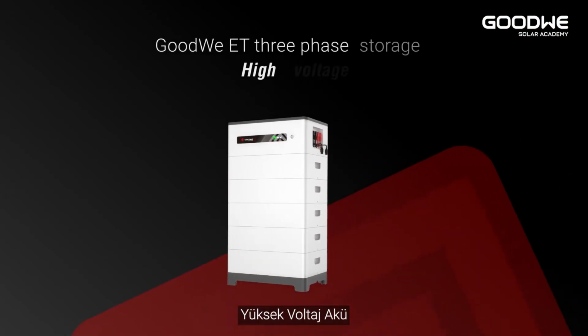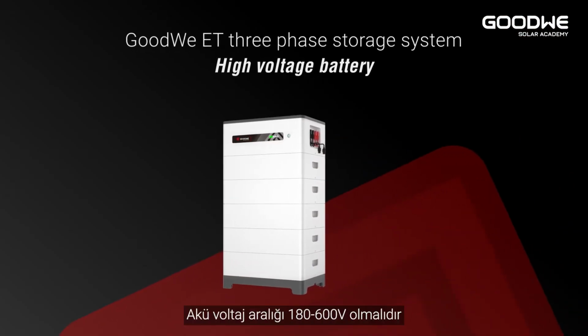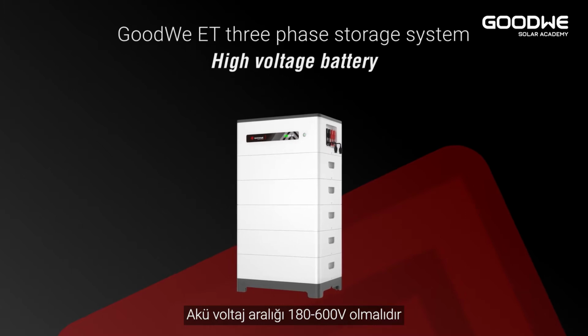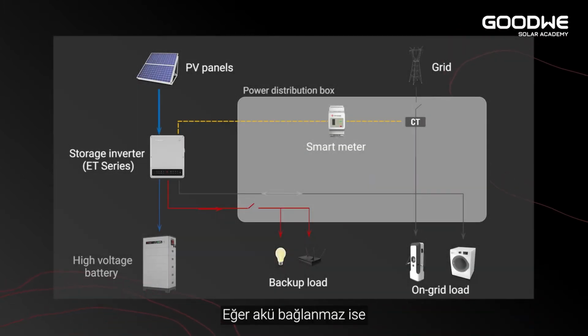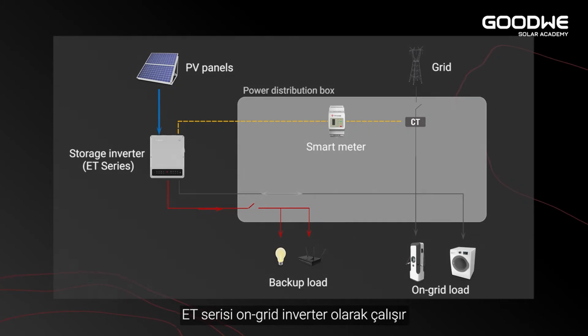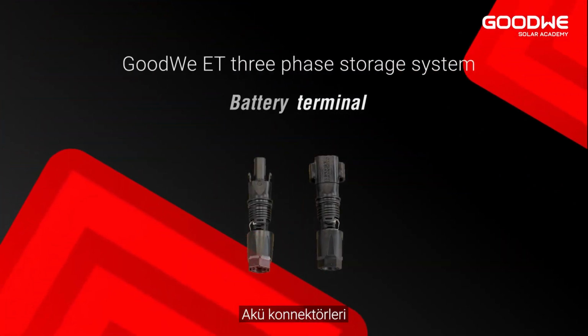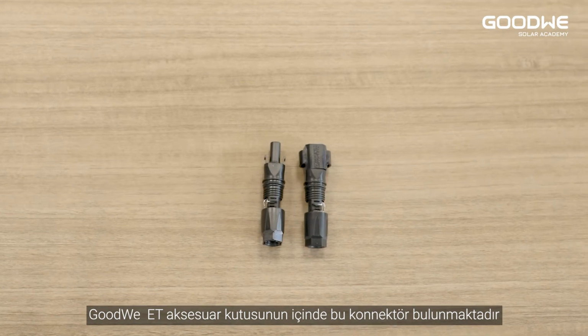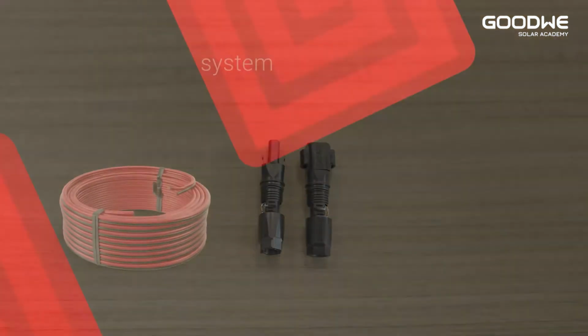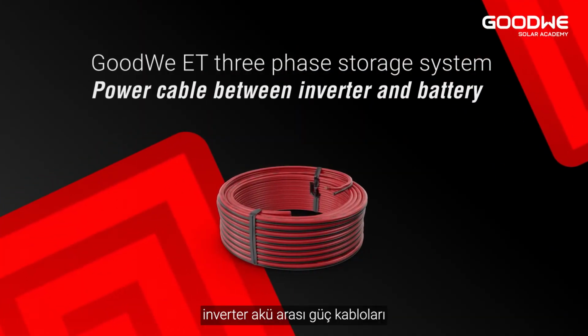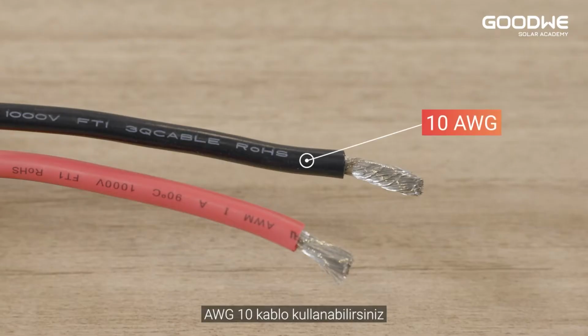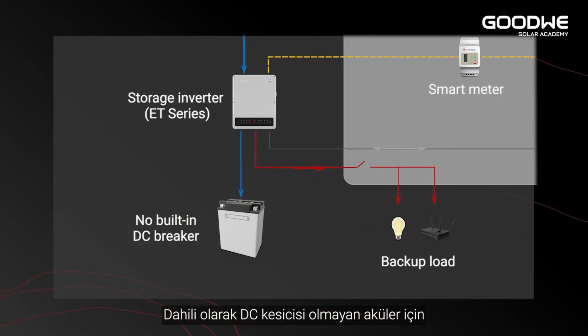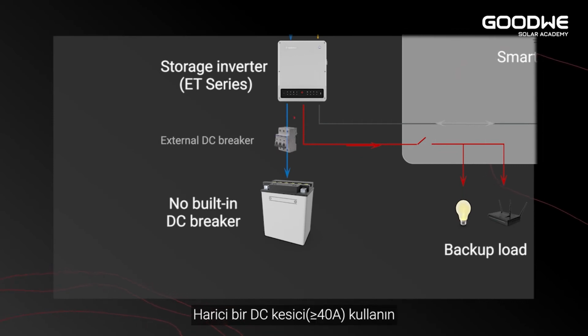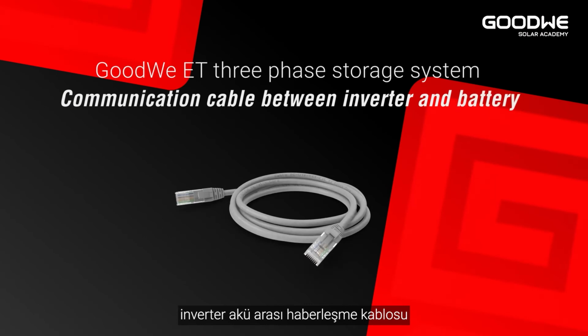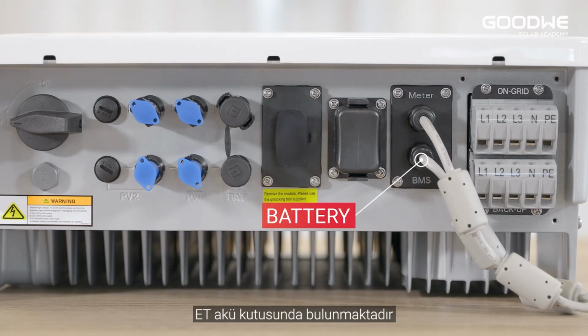High voltage battery. This is optional. The battery voltage should be between 180 and 600 volts. Without the high voltage battery, the ET is a grid-tied inverter. Battery terminal. GoodWe provides the battery terminal in the ET accessory box. Power cable between inverter and battery. Please use AWG10 cable. For batteries without a built-in DC breaker, make sure that an external DC breaker is connected. Communication cable between inverter and battery. Integrated in the ET battery communication port.